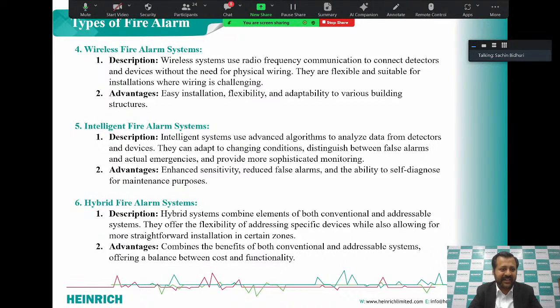We have the intelligent fire alarm system. The intelligent fire alarm system is basically a much more advanced version which can adapt to changing conditions and distinguish between false alarms and actual emergencies. So it can provide better, clearer monitoring. No false alarm is there. And now the last one is the hybrid fire alarm system. In the hybrid fire alarm system, we are using both systems, conventional as well as addressable. It is obviously more economical. It has better functionalities now, and we have a mix of both conventional and addressable systems in this.